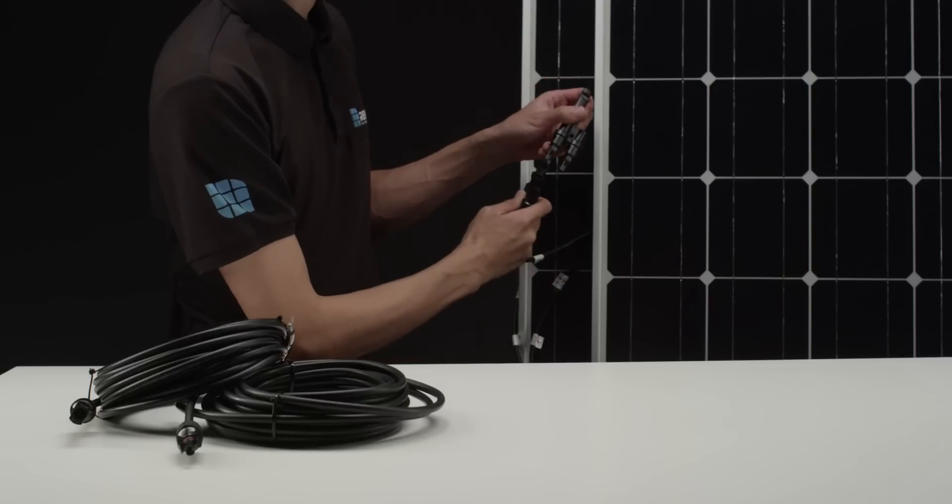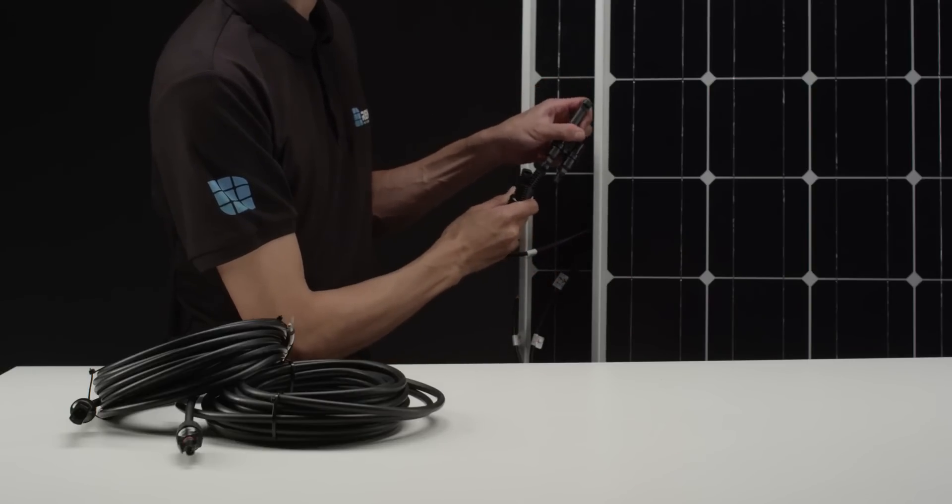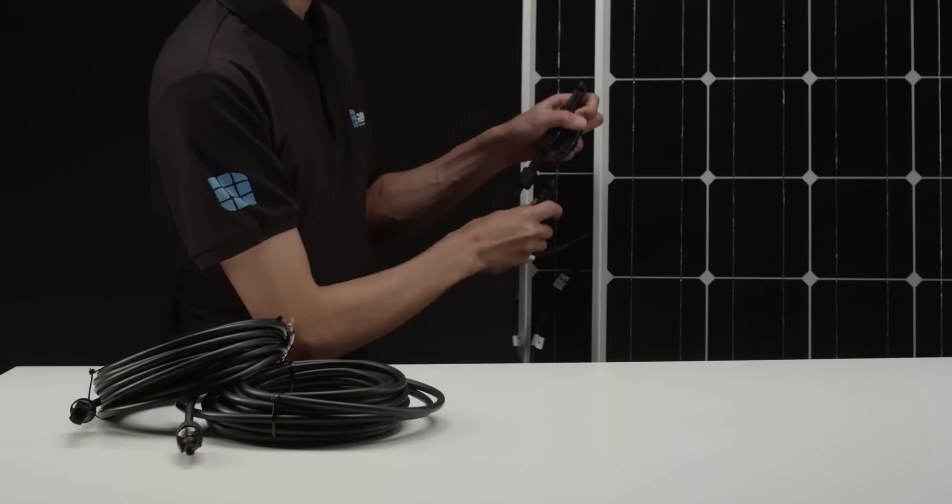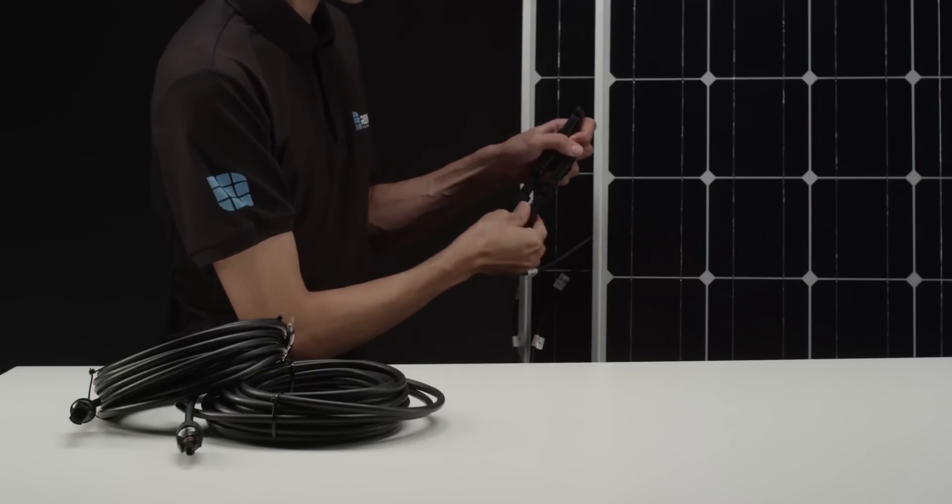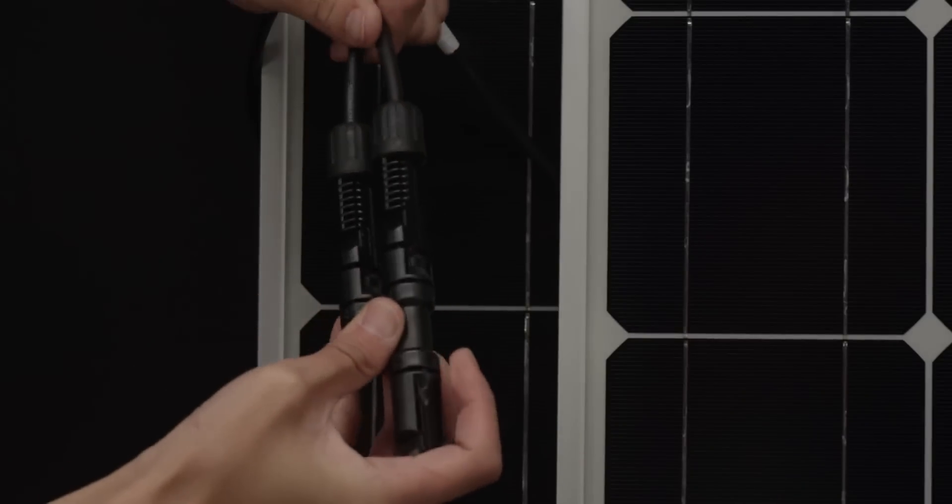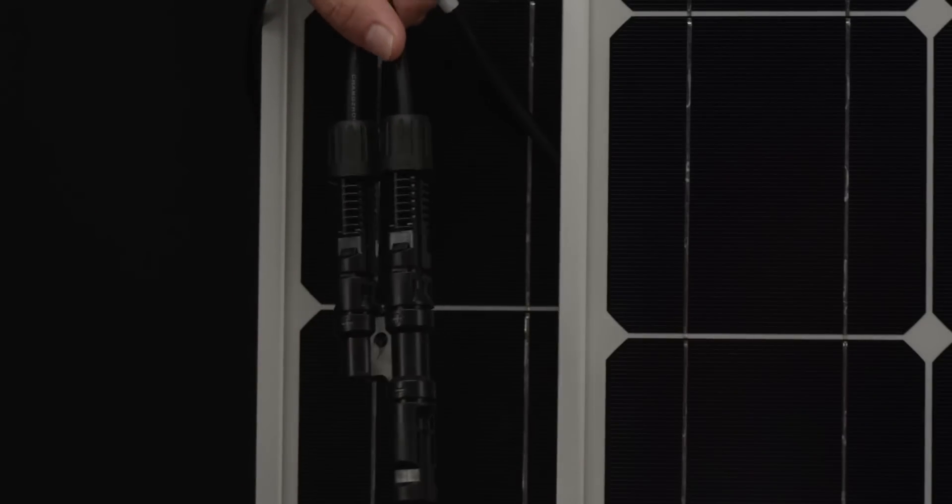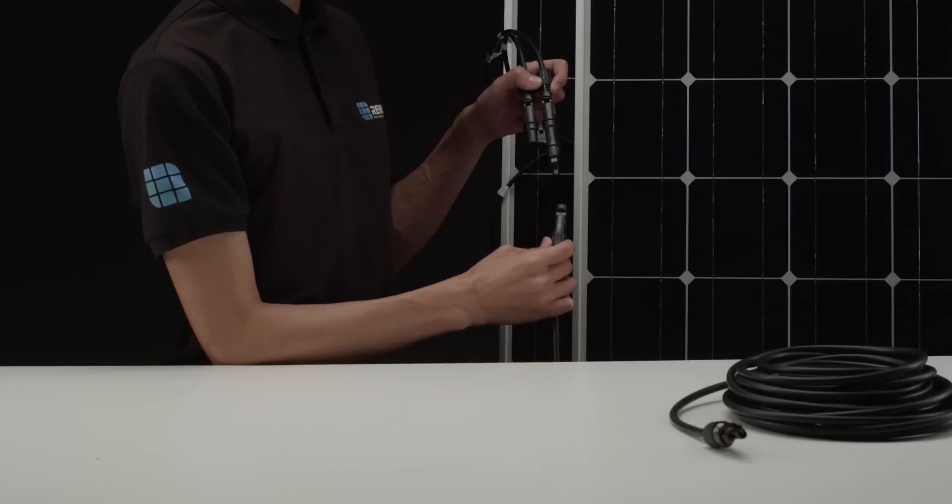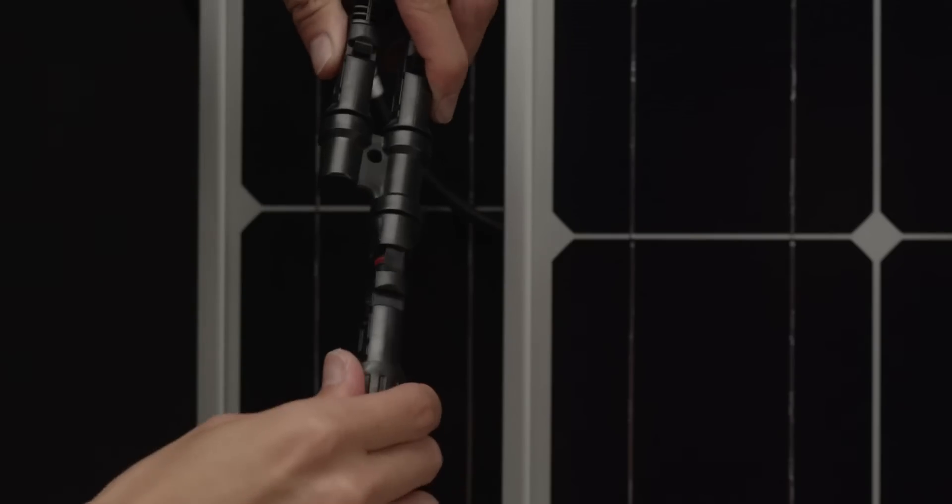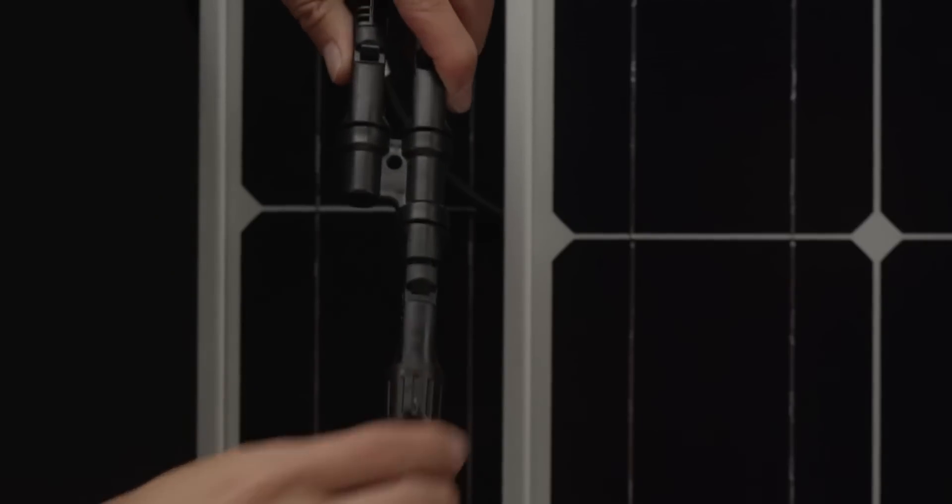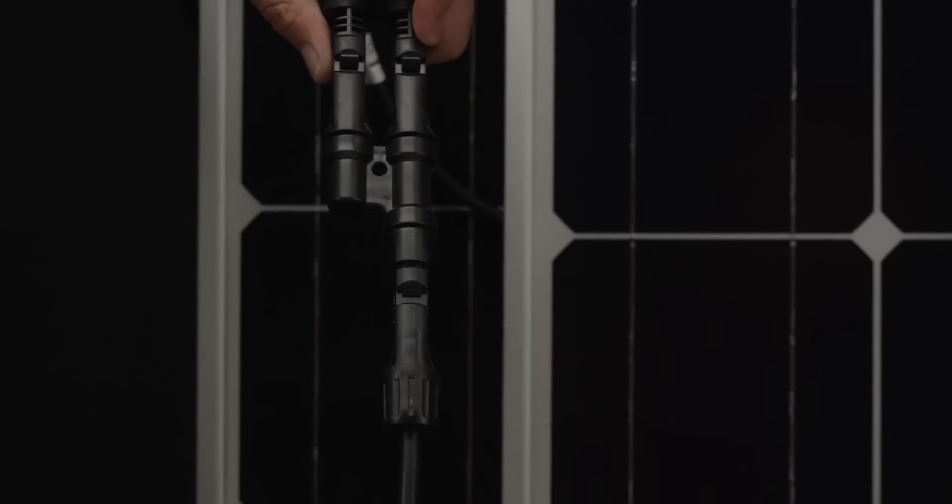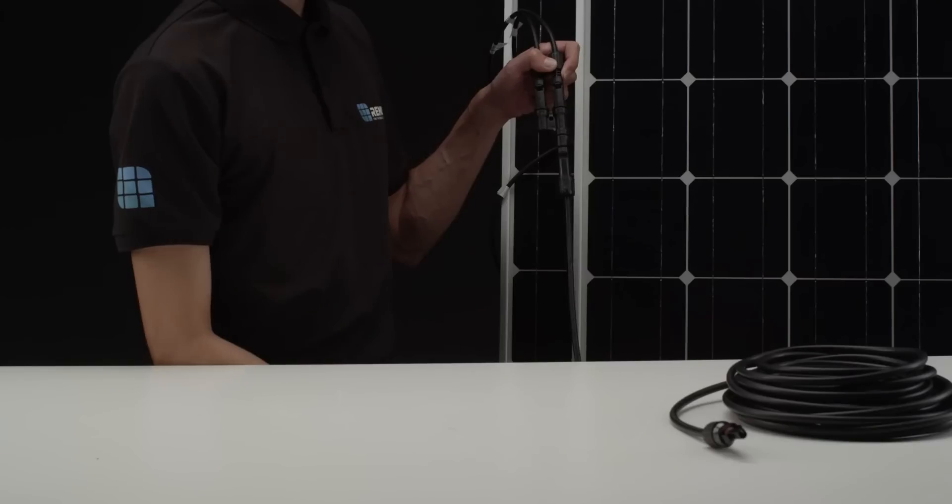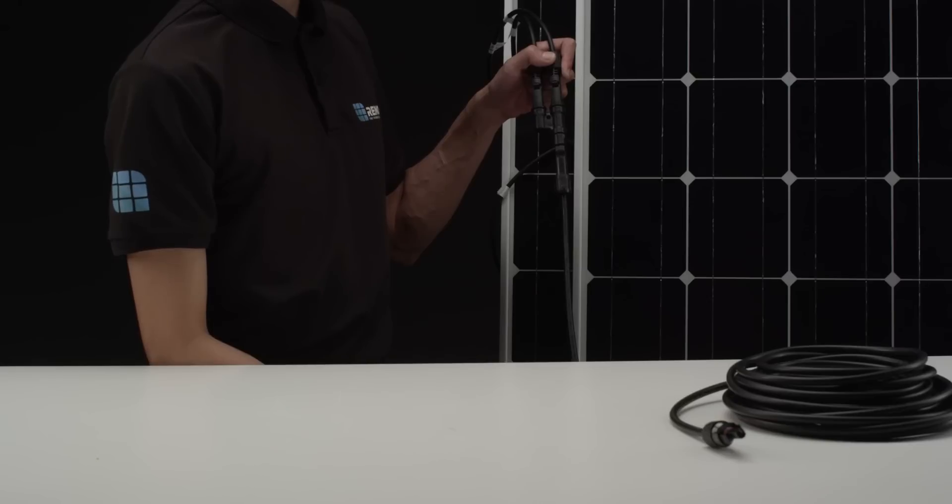In this next step we will connect both panels in parallel by using the MC4 branch connectors. Connect all positive male connectors to a branch connector and connect all negative female connectors to the other branch connector. Next, connect the included adapter kit to the branch connectors. Don't get confused as the branch connectors are the same polarity despite switching MC4 connector on the adapter kit.